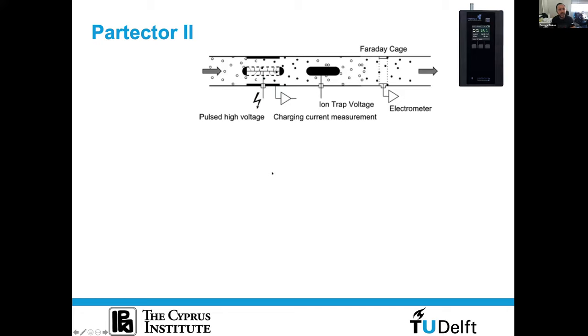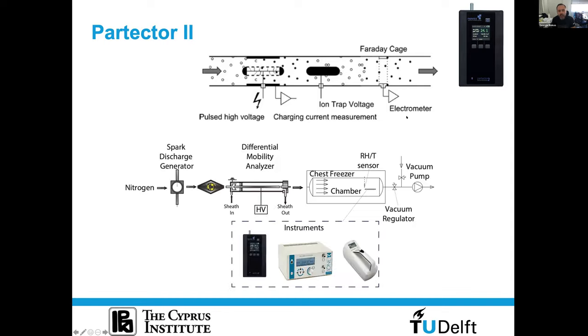Another instrument we have been testing is the Partector from Naneos. It is a very miniaturized instrument — slightly bigger than a pack of cigarettes. Inside, it has a corona charger that unipolarly charges all incoming particles, an ion trap or precipitator that is switched on and off to perform crude sizing of particles, and a Faraday cage electrometer. The Partector reports both the mean size and the concentration of the particles.